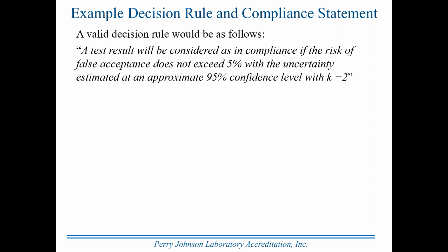Now, the expression of the confidence level and the value of K is a requirement that comes from ILAC P14. So technically, if you say that it's within 5% risk of false acceptance, and if that's true, you don't have to know what the confidence level was or the K value in order to determine that. If the laboratory estimates the risk of false acceptance and tells you it's within 5%, then that's fine. But ILAC P14 requires that the confidence level and the value of K be published on the certificate.